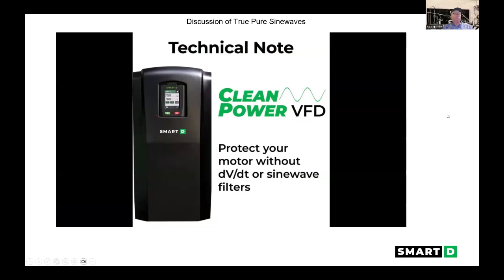So the reason I bring that up is over time, I've been involved with thousands of VFD installs, and what always comes up is a lot of times when you get multiple VFDs. Some of the first ones we ever did for Milton Bradley Toys, we ran into tremendous harmonic content on the front. So the way to patch that, we were putting line reactors, active front ends to clean that up, because it creates radiated noise out through the system on the primary side with the diode front ends.